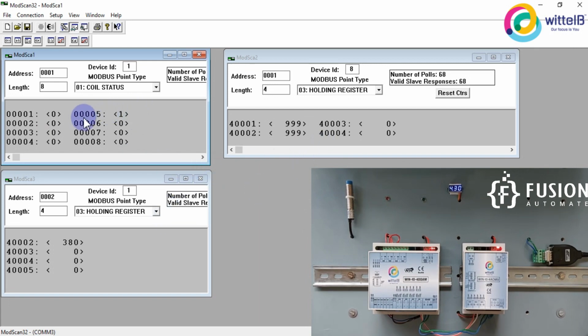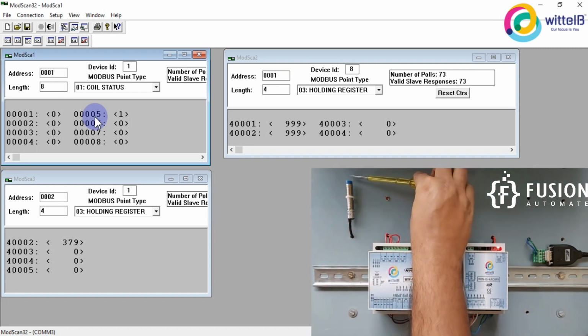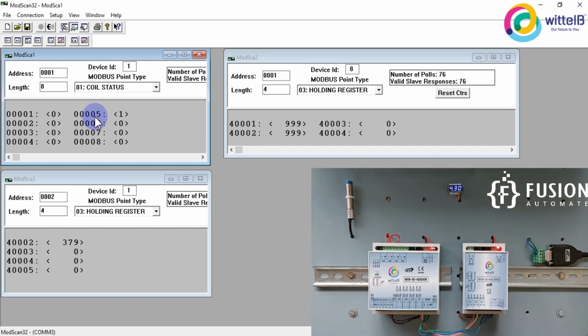Now you can see here 05 is associated with the DI1. My sensor is an NPN sensor, so if the part is not present on the sensor, it will give me 12 volts, and if the part is present, it will not give me anything. As you can see, the value of 05 is 0 now. Now the value of 05 is 1. So this sensor is connected with the DI1, and this is the NPN sensor. Whenever the part is not present on the sensor, it will give me 12 volts output, so that is why you see high, 1, true here. But whenever the part is present, it will not give me anything, so it will give 0. That is why you see false, or an off state.